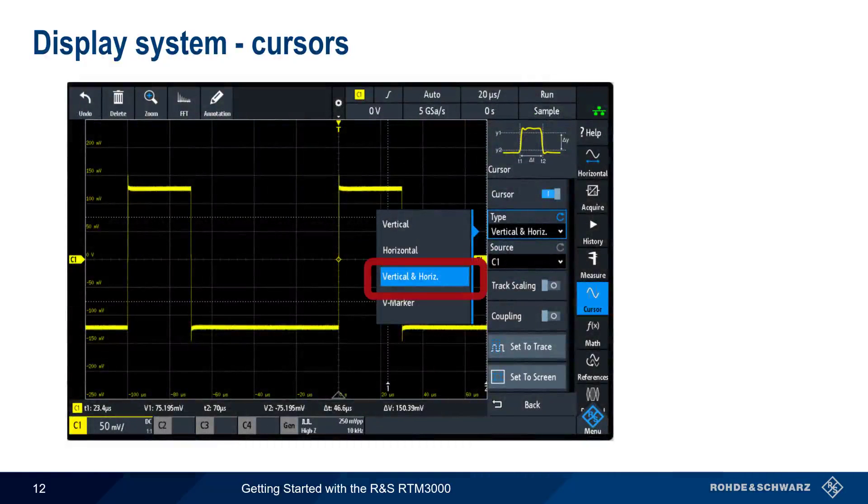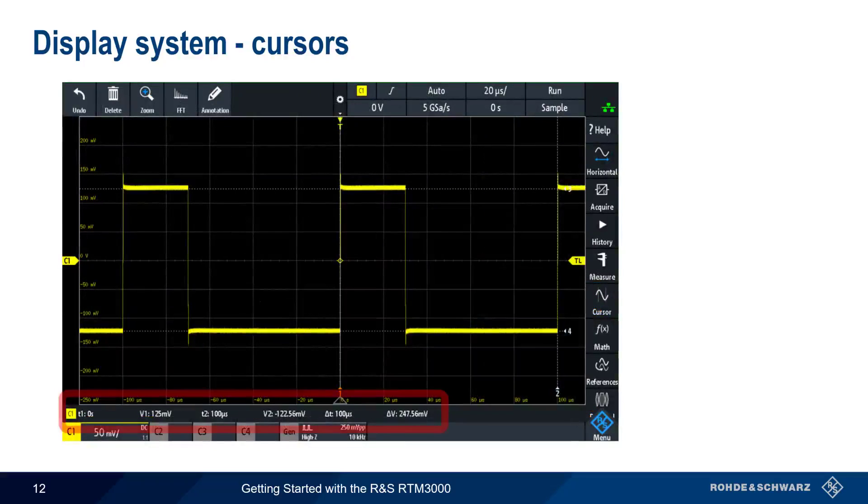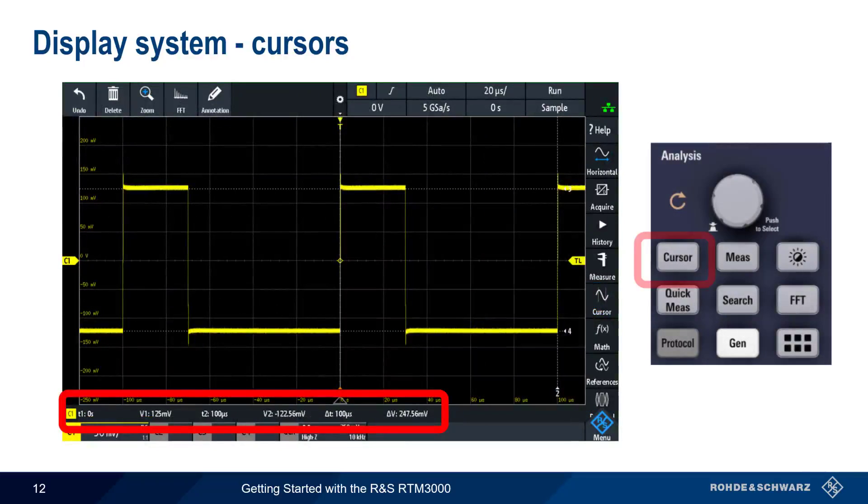Using cursors is a significant improvement compared to counting divisions. By using two sets of cursors, vertical and horizontal, we can get results much more quickly and more precisely. We enable cursors using the cursor button and adjust them using the cursor knob, pushing the button in to toggle between cursors.